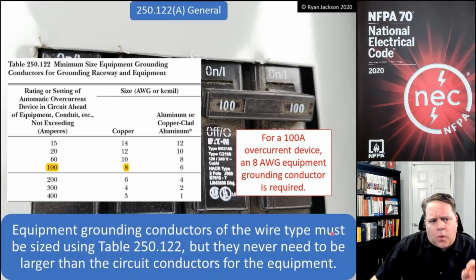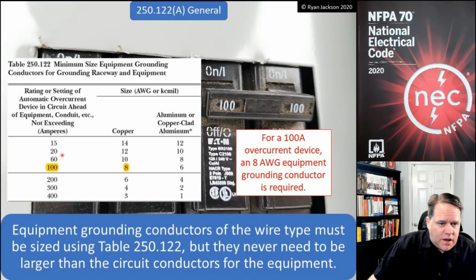I want to point out one little thing though. Notice that if I have a breaker or fuse that's rated 15 amps, I use a 14 gauge copper. And for 20 amp, I use 12 gauge copper. And for 30 amps, I use 10 gauge.